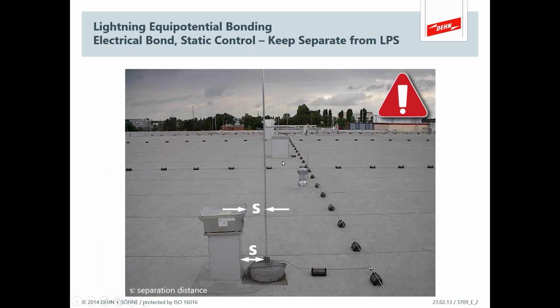And then lightning equipotential bonding. This is, again, one of our pillars. You can see things that you want to bond to your lightning system. If it goes past the flange at the roof, or past a metal structure that's probably going to get hit anyway, like this vent stack, it is probably not that important in this application. It might just be a hot air vent stack. But if that were a natural gas burn-off stack, that's a different conversation. You don't want to put an ignition source there.